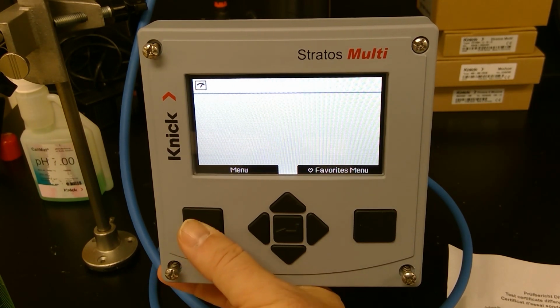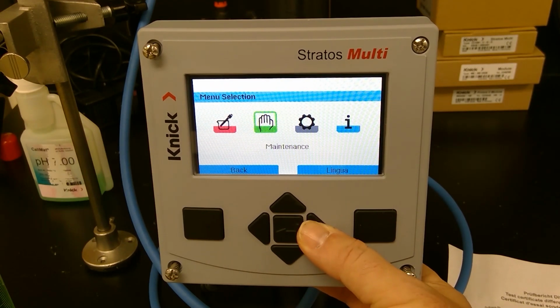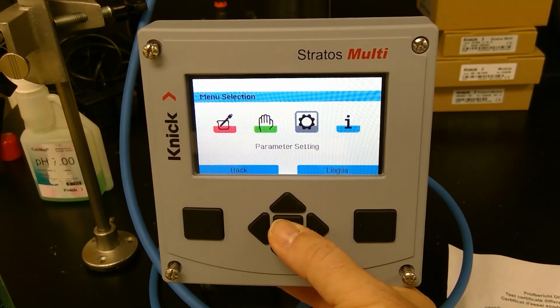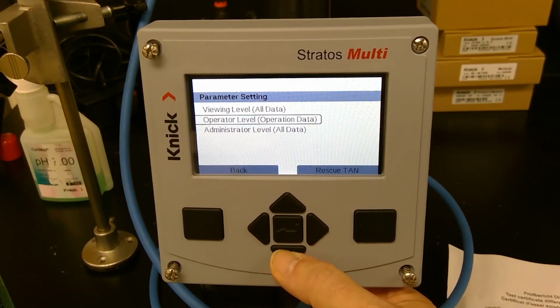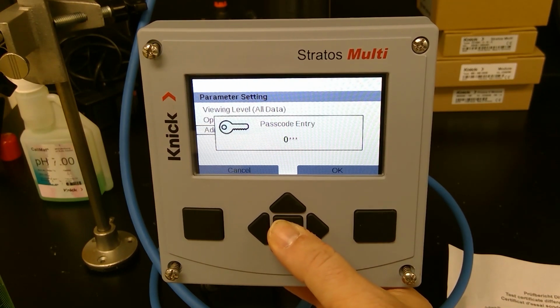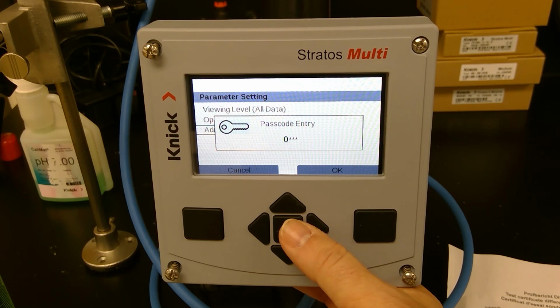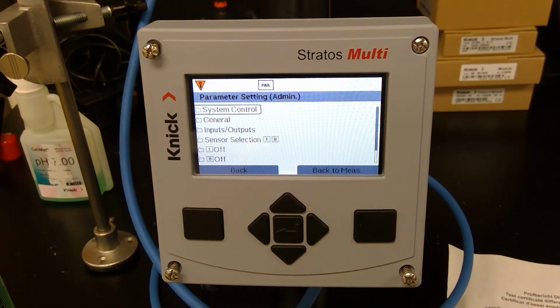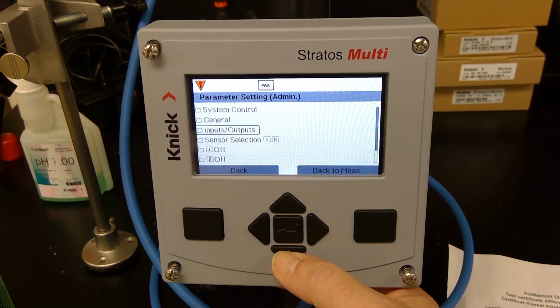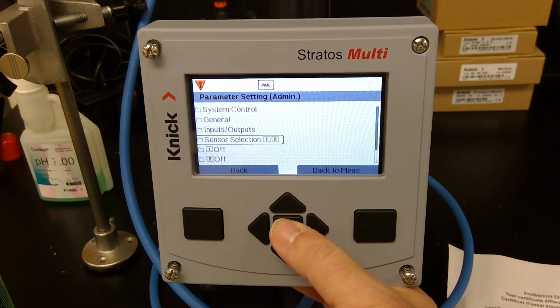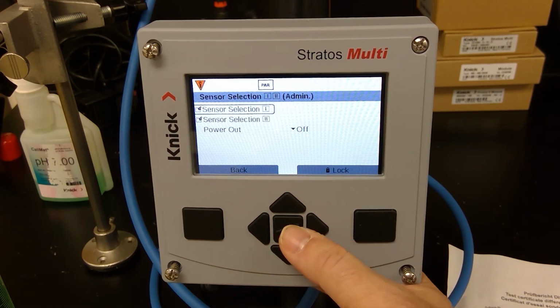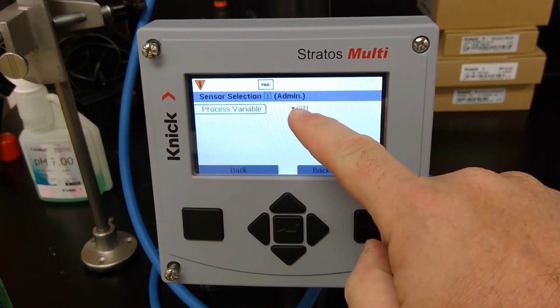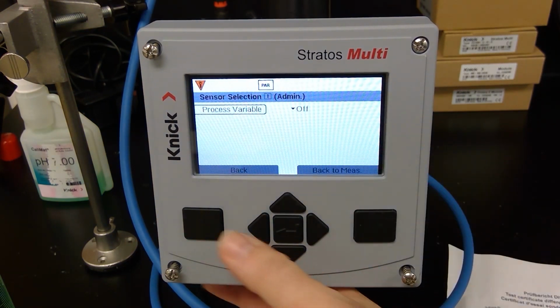So we'll go ahead and start by hitting menu, go into parameter settings. I'm going to go down to administrator level, and I've got the passcode turned off. Actually, I have it set to 0000, so all I have to do is hit enter. I scroll down to sensor selection, and as I said, we're going to be using channel 2, so I need to make sure that channel 1 is turned off. In this case, it is.